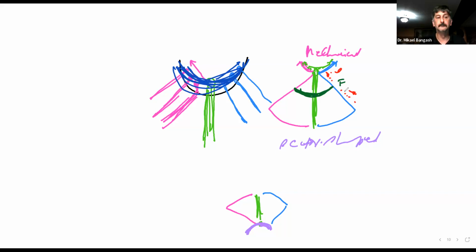Did that make sense? Yes. Because this transducer that we were using here was made just to focus at this depth, let's say at a depth of 3 centimeters. Which means you will not be able to focus at 2 centimeters, 1 centimeter, half a centimeter, neither at 4, 5, 6, 7, 8 centimeters. This was the depth at which the beam will be focused. So you can't change the focal depth or focal point, because that's fixed.